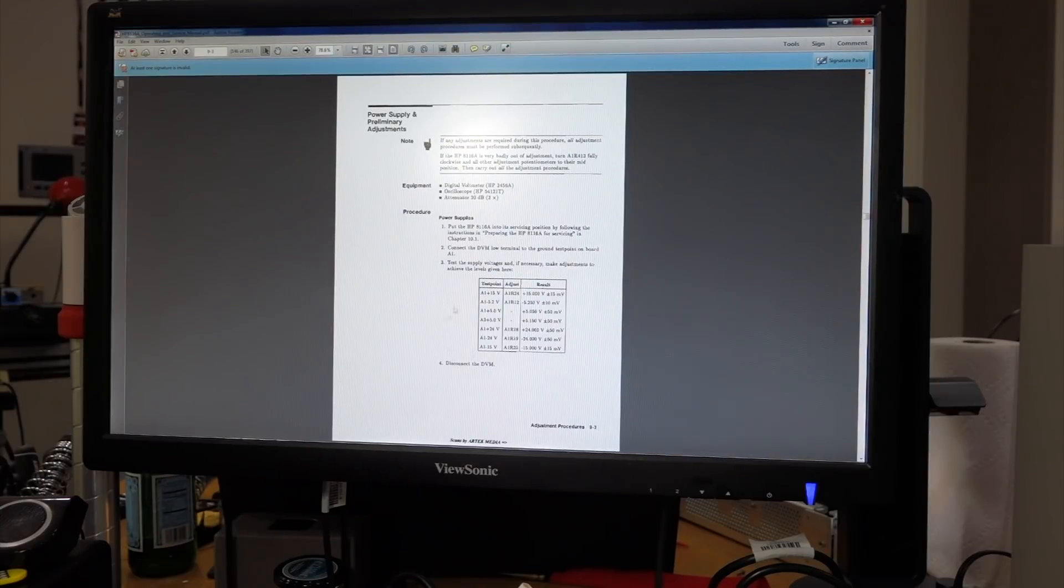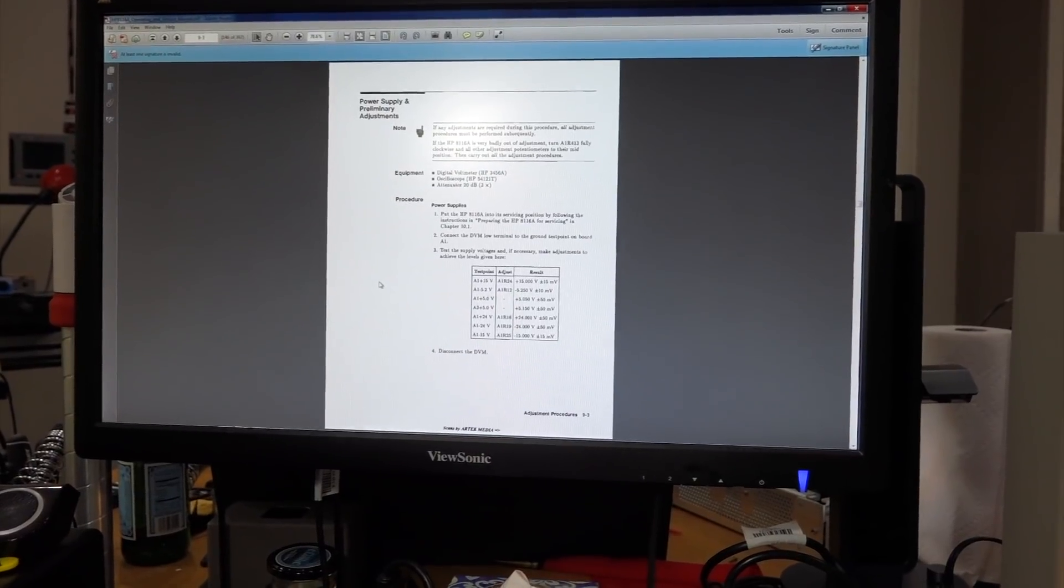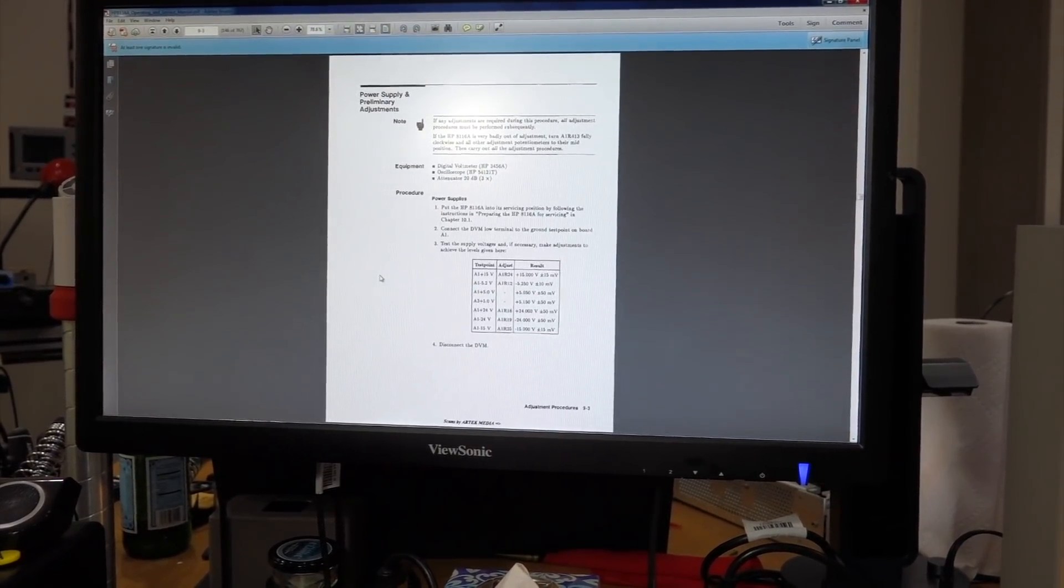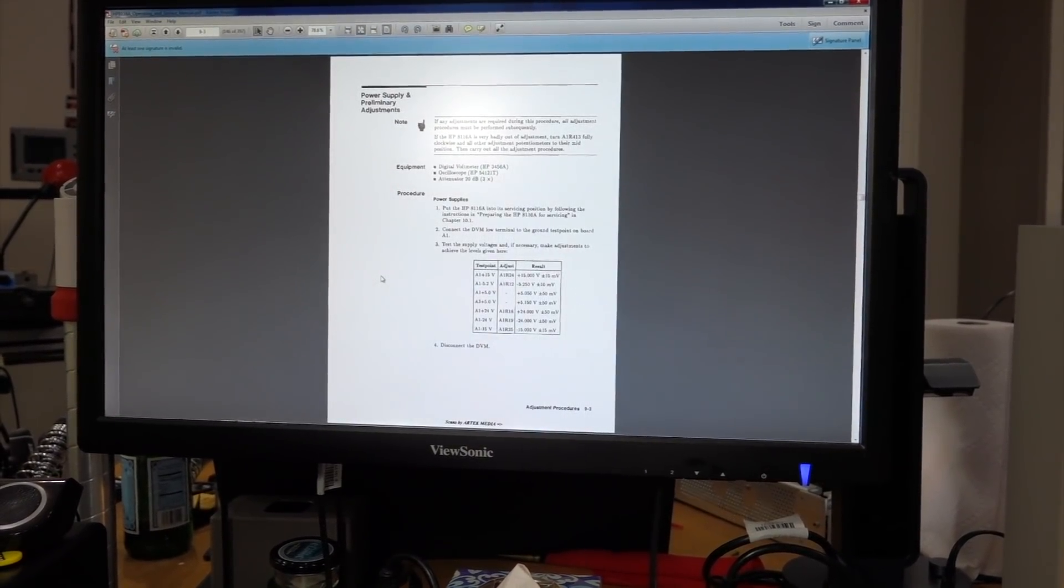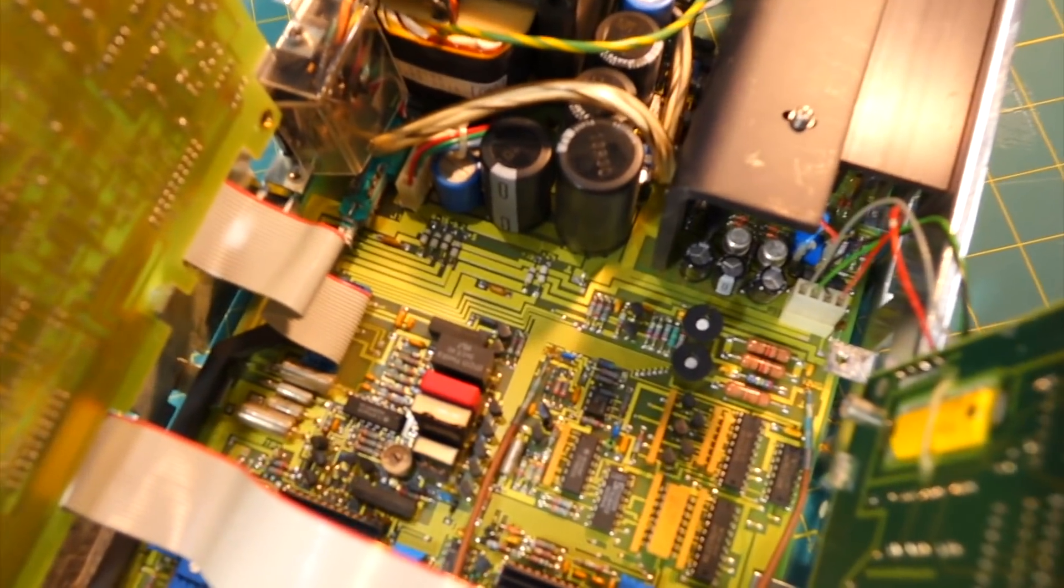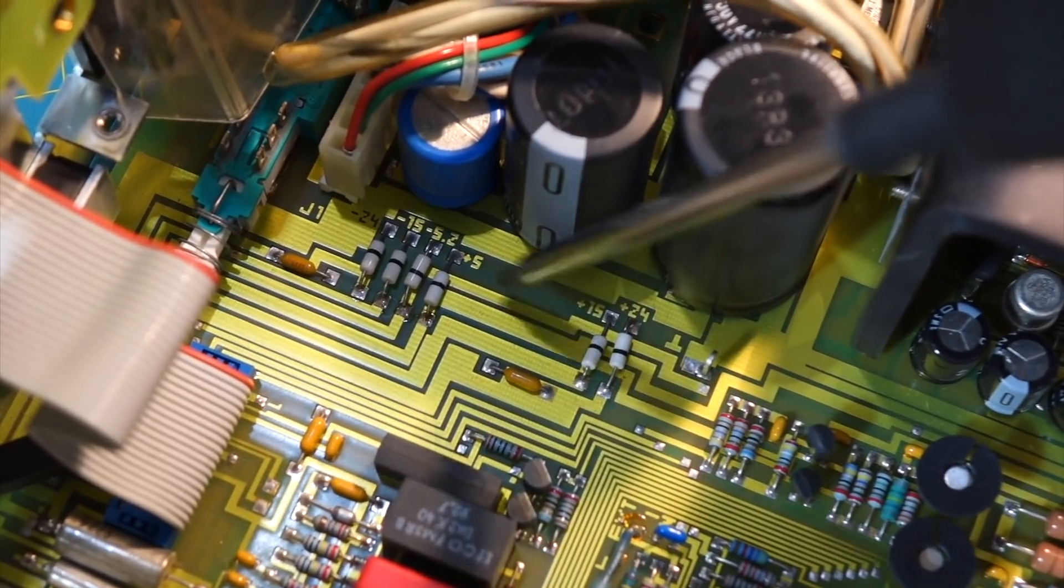The first thing you have to do is get the power supplies calibrated, which is of course easy peasy stuff. At least for power, they made it easy to check for you. You can see all the test points, ground, and all the voltages are shown here, so it shouldn't be too hard.